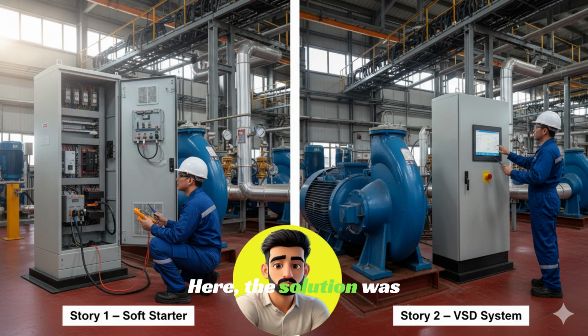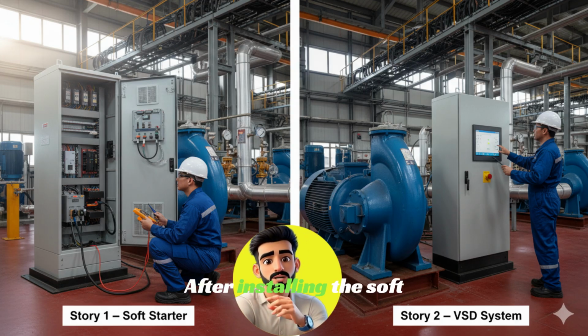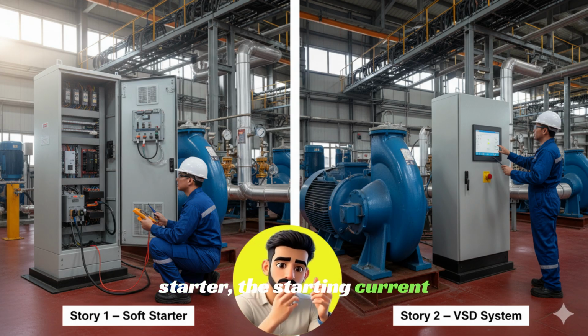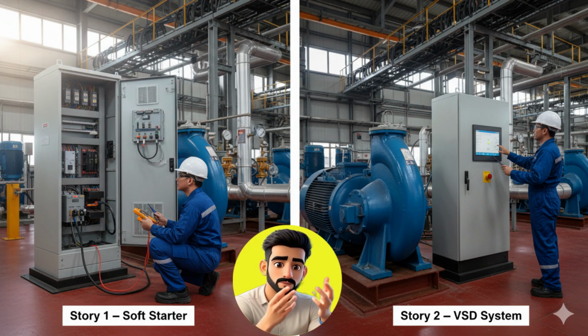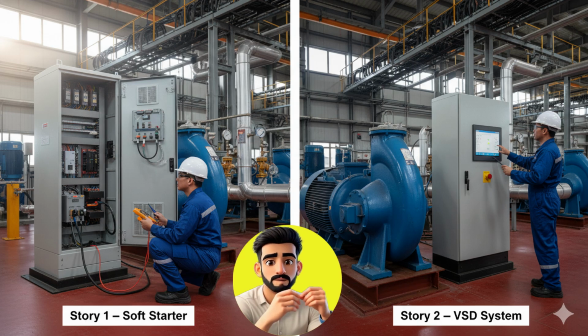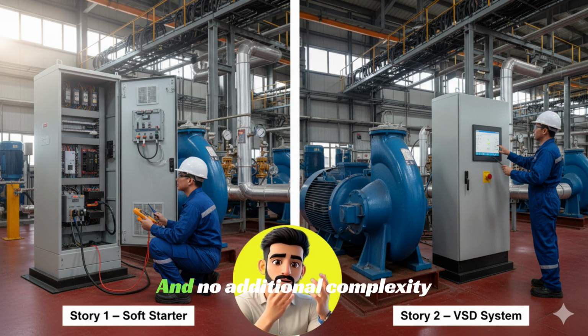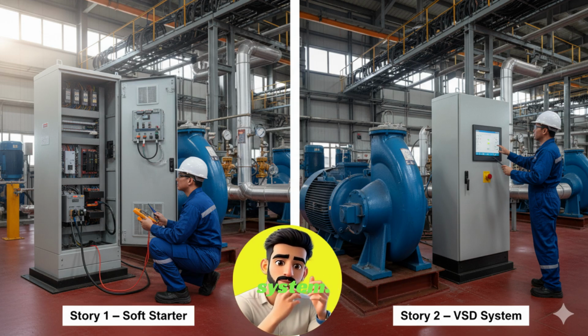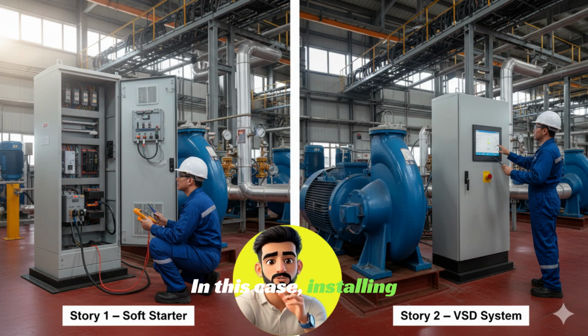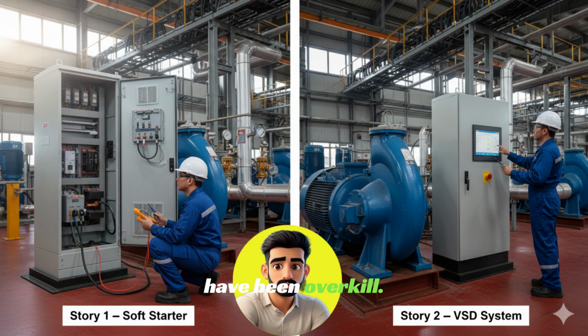Here, the solution was very simple. Soft starter. After installing the soft starter, the starting current reduced to less than half. Voltage dips were controlled. Transformer stress reduced, and no additional complexity was added to the system. In this case, installing VSD would have been overkill. The requirement was simple, and the solution should have been simple too.